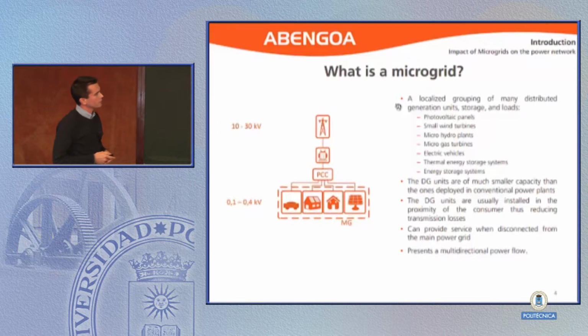The major characteristic of the microgrid is the point of common coupling, where the microgrid connects to the power system, and the fact that it can run in both connected and disconnected mode. Seen from the power system side, the microgrid can look like a load or a generator depending on power management. If consumption is larger than generation, we have a load; if generation is larger than the load at the microgrid level, we can see it as a generator.